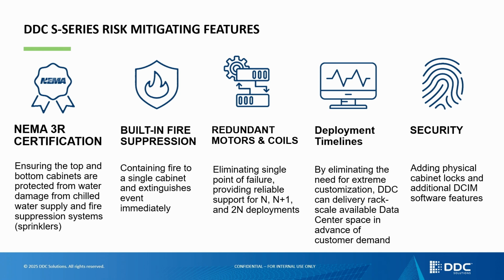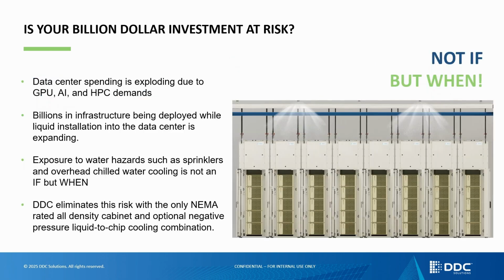Right now, figuring out what customers need and having rack-ready capacity in our colos and enterprise data centers is difficult because there's so much variation in the hardware coming out. But if you have a rack that provides air cooling up to 100 kilowatts and direct liquid integration for a variety of partners, fitting any type of housing enclosure, you can start bringing capacity online and rolling customers in as they go—something we're trying to harken back to in the hosting industry. Because the software manages whether those cabinets are active or under thermal load, you're not wasting energy or water by bringing this capacity online.